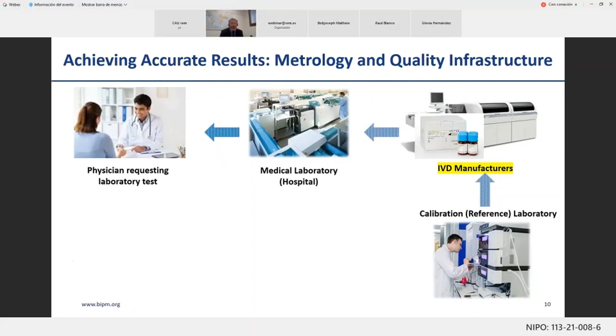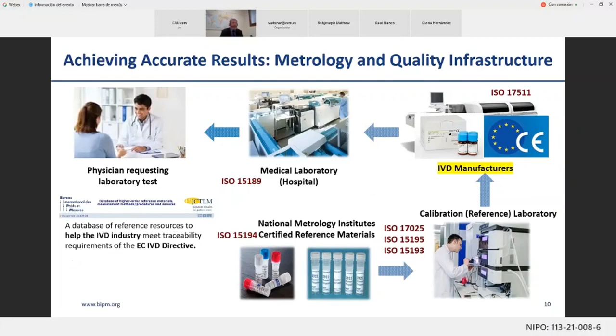An important point to note is that this area is regulated. And one of the regulations that I'll come back to, an important one, is that within the European Union, which is the IVD directive, which was the first one to state clear metrological requirements for calibrators and control materials used in laboratory medicine testing. I'll also talk later on about the Joint Committee for Traceability in Laboratory Medicine, which is a database which contains those methods, materials and services which can be used for traceability requirements. And finally, because this particular regulation is implemented within the European system, the technical requirements themselves are found in harmonized standards. So I'll also talk a little bit about the technical requirements of those harmonized standards for these materials, methods, and services, which are behind the scenes and enable accurate measurements in the laboratories in which your samples will eventually be tested.